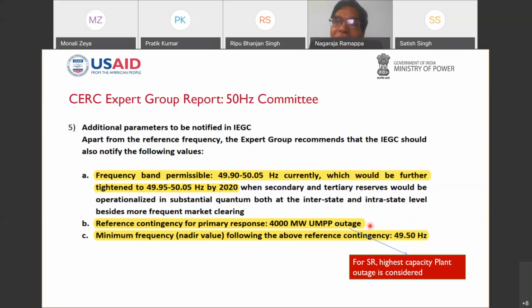And as part of that, for the secondary control, there is one more pilot project that has happened. Even in the northern region, at one of the thermal power plants at Dadri, AGC, automatic generation control, was implemented. And in the southern region, under the same GTG RISE project, both the Sharavati and Varahi hydro projects are having automatic generation control implemented. The pilot was successful. Now, for all India, the reference contingency for the primary response, a 4,000 megawatt UMPP outage, was considered. For the southern region, the highest capacity plant, Ramagundam, is being considered. Now, the nadir frequency in the 50 Hertz committee report has been defined as 49.5 hertz. Therefore, we have done the studies not just for 49.5 hertz, but also for 49.2 hertz and 49.8 hertz. Next, please.